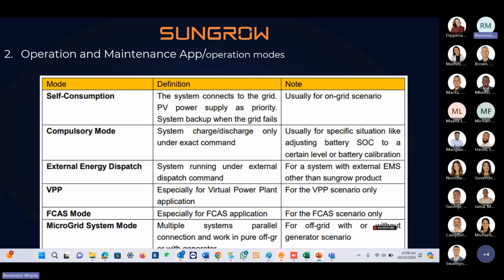And then for the other operation modes, we have self-consumption, which is the normal self-consumption, whereby the system tries by all means not to take power from the grid. And then we have the compulsory mode, whereby we prioritize charging or discharging the batteries depending on what you command the batteries to do. So these are the only two applicable solutions that we have for the South African market, which is self-consumption and compulsory mode. So on self-consumption, the system prioritizes not using the grid basically. No matter what, even if grid fails, even if grid is available, the system tries by all means to use PV and the battery to supply the loads.